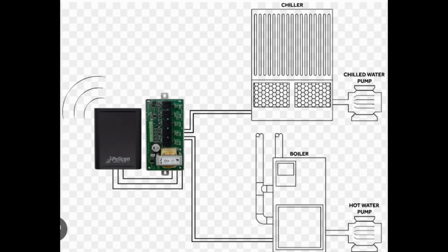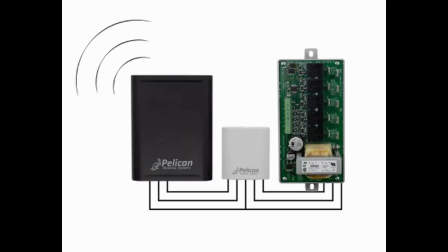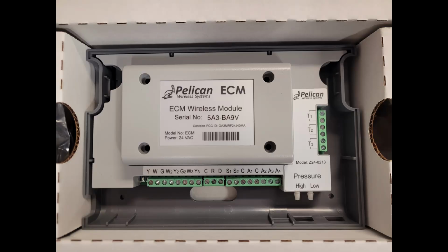For constant volume applications, control of the boiler, cooling tower, and all related pumps can be achieved with the Pelican Power Control module. If flow interlock control is desired, a TA1 can be placed on the same data circuit as the power control module to monitor a binary flow device. A TC1 thermostat and Pearl combination can be used to monitor the building water loop supply and return temperatures. If modulating control of variable speed pumps or cooling tower fans is needed, the Pelican plant controller can handle it.